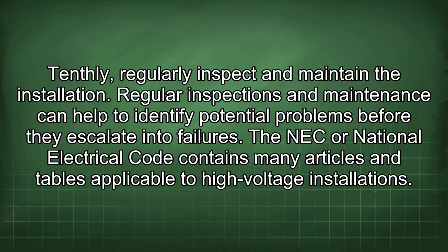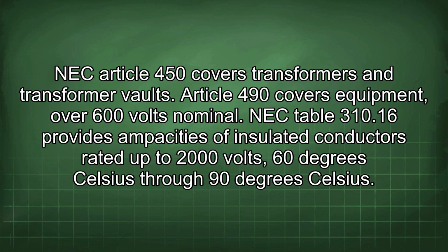The NEC, or National Electrical Code, contains many articles and tables applicable to high voltage installations. NEC Article 450 covers transformers and transformer vaults. Article 490 covers equipment over 600 volts nominal. NEC Table 310.16 provides ampacities of insulated conductors rated up to 2000 volts, 60 degrees Celsius through 90 degrees Celsius.